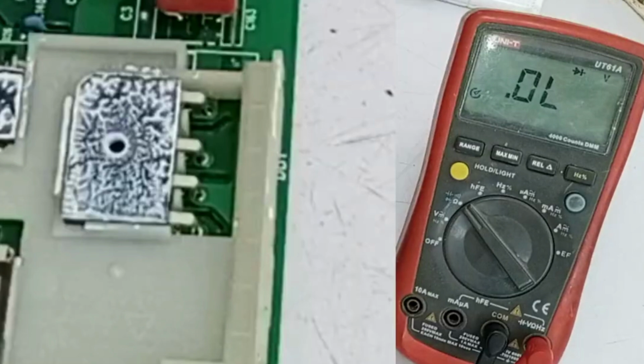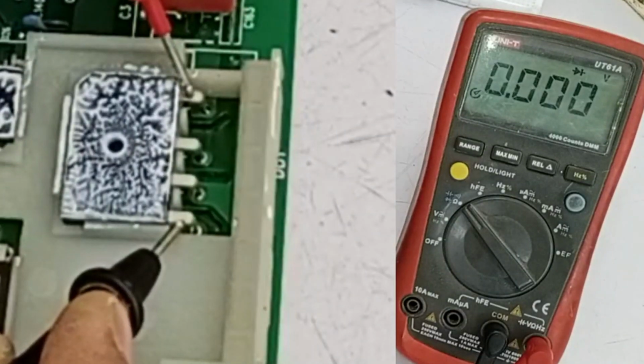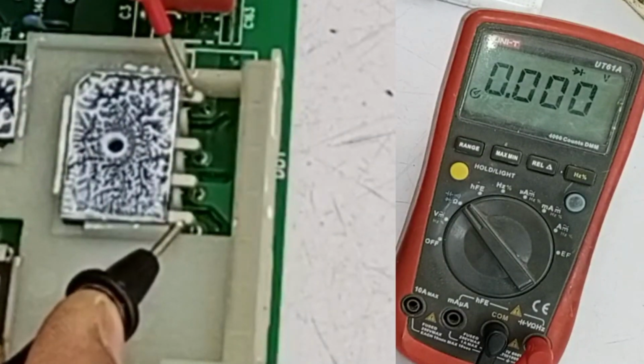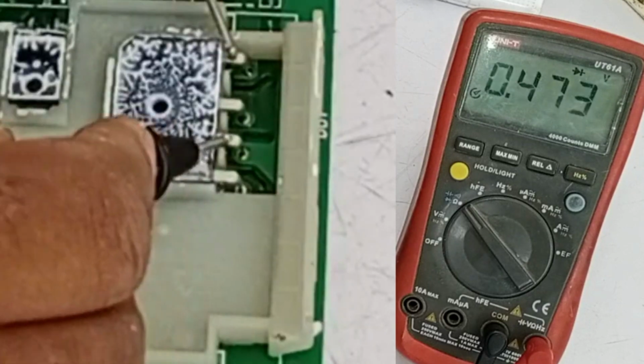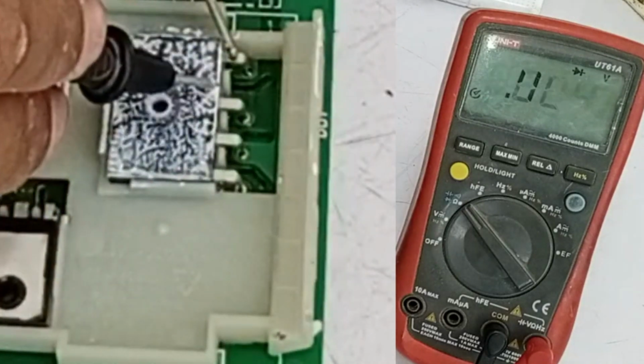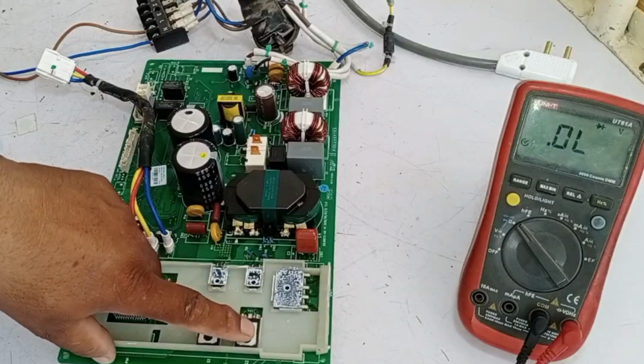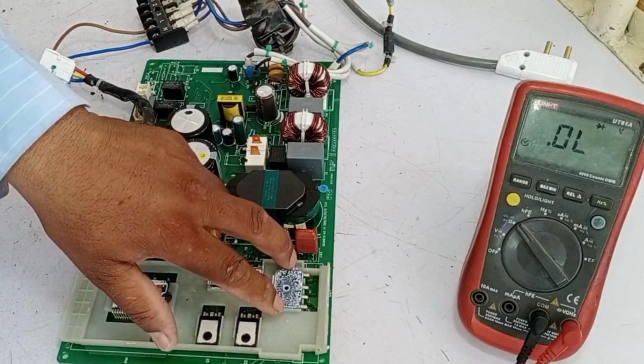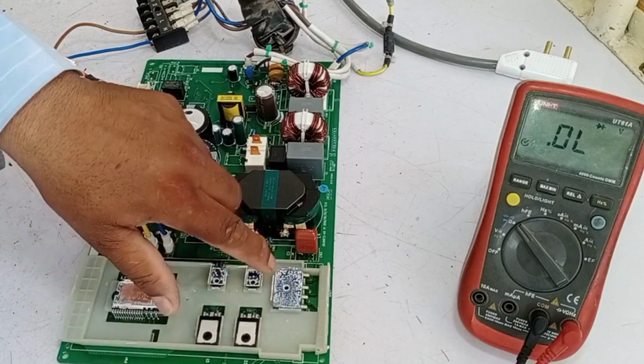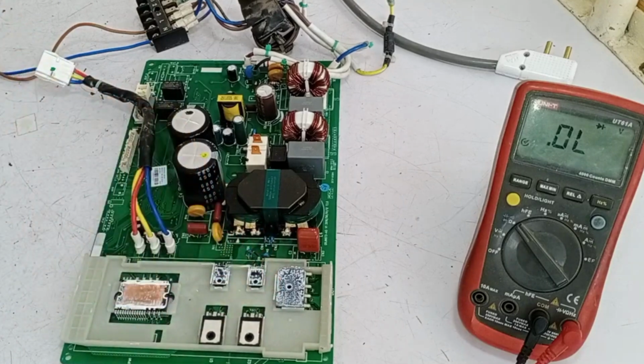Next, I'll test the bridge rectifier. When I place the probes, it's showing 0 at one point, which isn't a good sign, but the other point is showing the correct reading. Since the first point is showing 0, there are two possibilities. After replacing the IGBT, I'll recheck the rectifier. If it's still faulty, then we'll go ahead and replace the bridge rectifier.